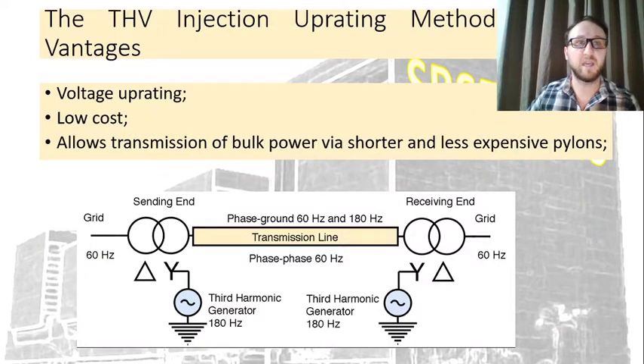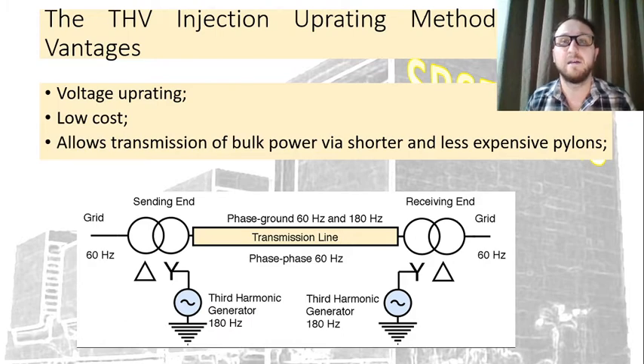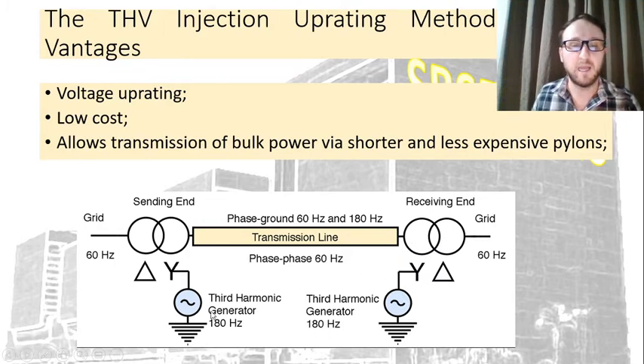As an alternative, we have the third harmonic voltage injection uprating method, which is based on voltage uprating. It is low cost and allows transmission of bulk power via shorter and less expensive pylons. Here we have a schematic: we have our 60 Hertz power system, and at the transformers we use a third harmonic generator, 180 Hertz, at the sending and receiving end.